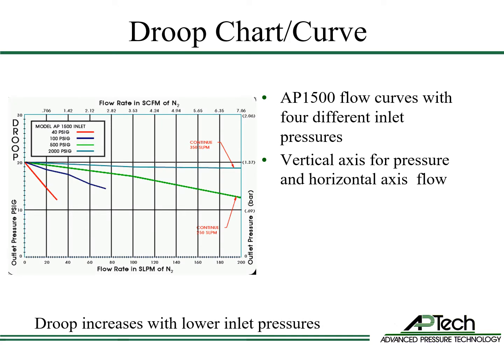This is a typical droop curve or flow curve. At the top, it indicates the gas used — in this case, nitrogen. Flow curves plot outlet pressure on the vertical axis and flow on the horizontal axis. This AP1500 regulator flow curve demonstrates the impact of four different inlet pressures with a 20 psi fixed zero-flow outlet pressure setting.